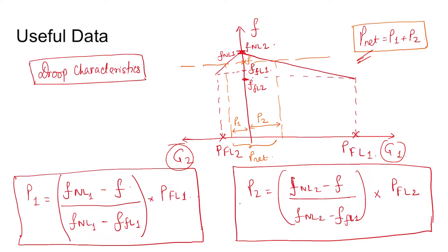As specified, the generator having larger capacity will share more load and the one with smaller capacity will share lesser load. This is given by the load shared by generator one: P1 = (f_NL1 - f) / (f_NL1 - f_FL1) multiplied by full load capacity of the generator.